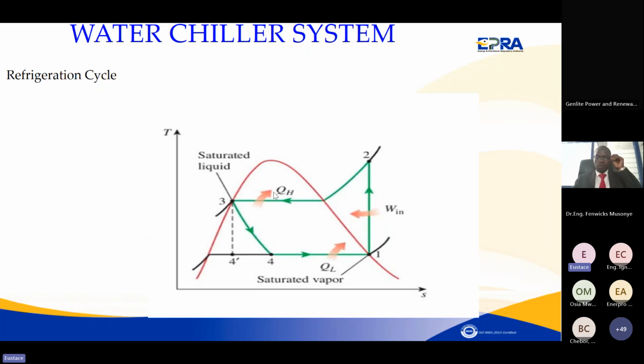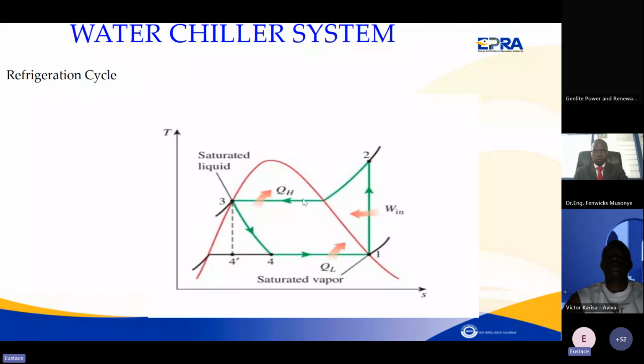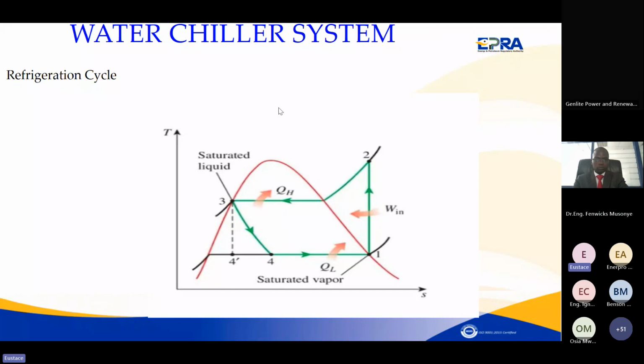And you want to release heat to the atmosphere or to the heat sink, which can be water or air, as easily as possible. So the efficiency of the heat transfer between the condenser tubes and the environment, or the heat sink, which can be water or air, should be as good as possible to minimize the amount of energy you need to put into the compressor. The reason we compress the refrigerant is to increase the pressure so that we can release heat at a higher temperature than that of the area being cooled. Because we are trying to transfer heat from a cold place to a hot place, you need to do some work. It's like pumping. Assume the heat is water. You want to pump water from low altitude to high altitude, so you need to do some work.